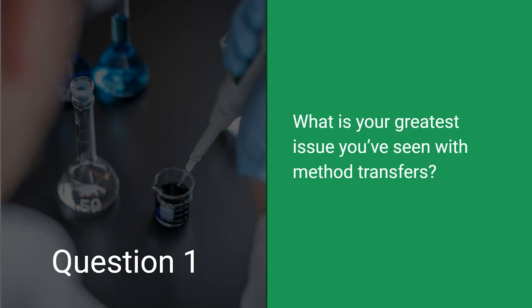The first question is: what is your greatest issue you've seen with method transfers? I would say that some of our biggest issues would be incomplete information sent to the receiving laboratory. Poorly developed methods will also cause issues with method transfers, as well as insufficient standards and critical reagents being available for use at the receiving laboratory.